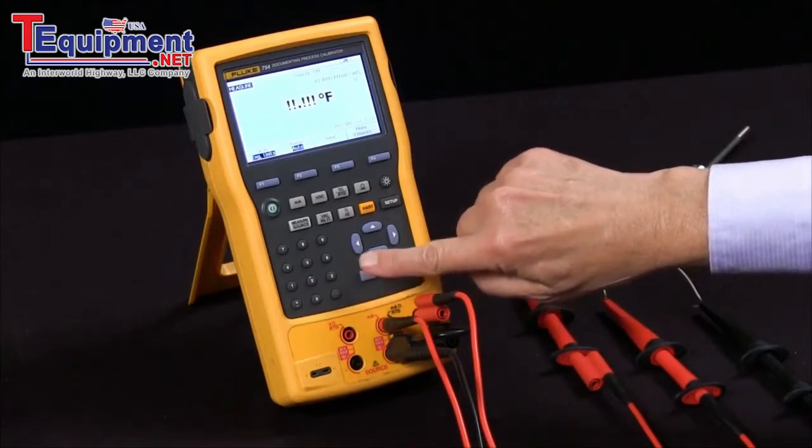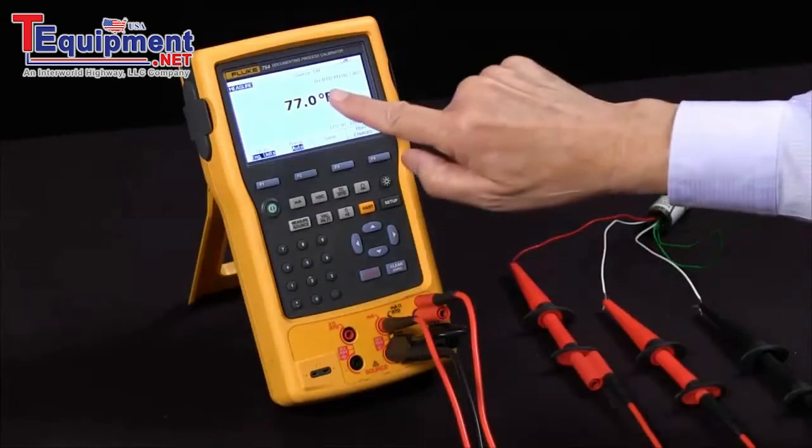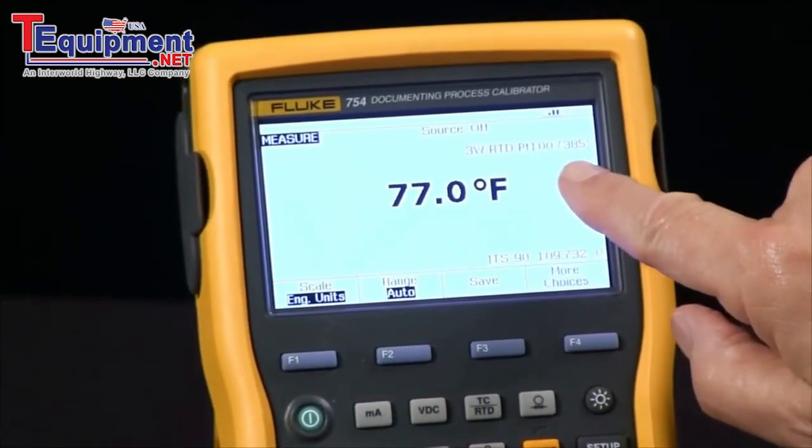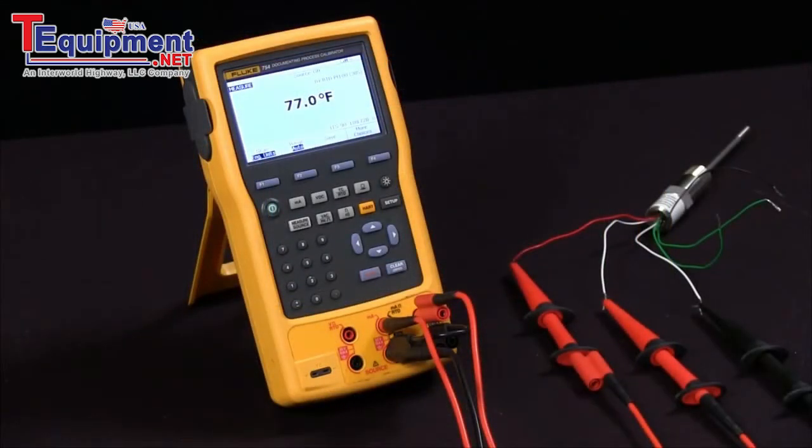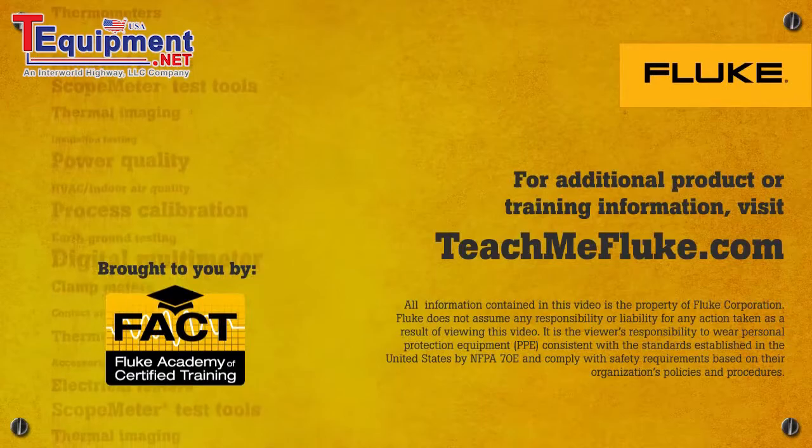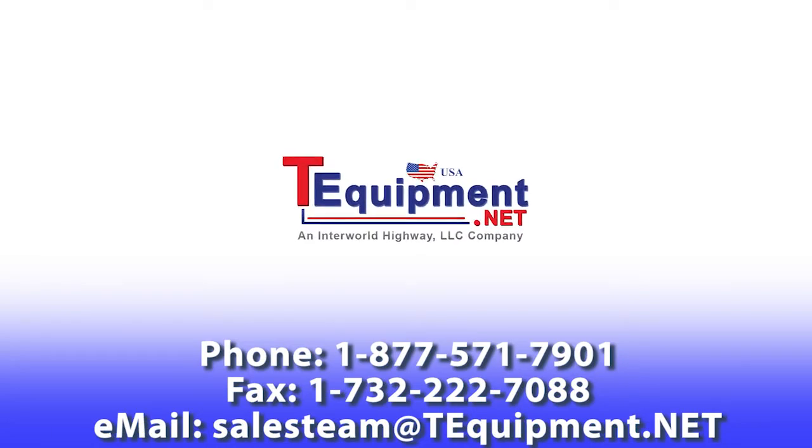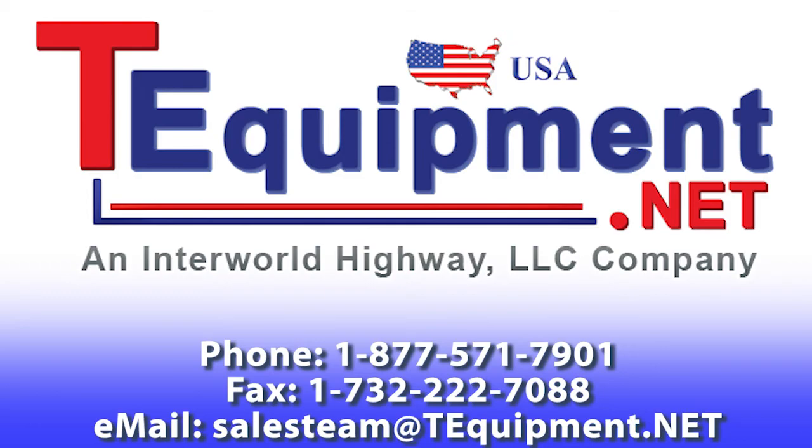I select three wire and it goes to the measure screen. It measures the RTD at room temperature, 77 degrees Fahrenheit. On the screen it shows three wire, RTD, platinum 100 ohm, 385. And that's how we measure an RTD.